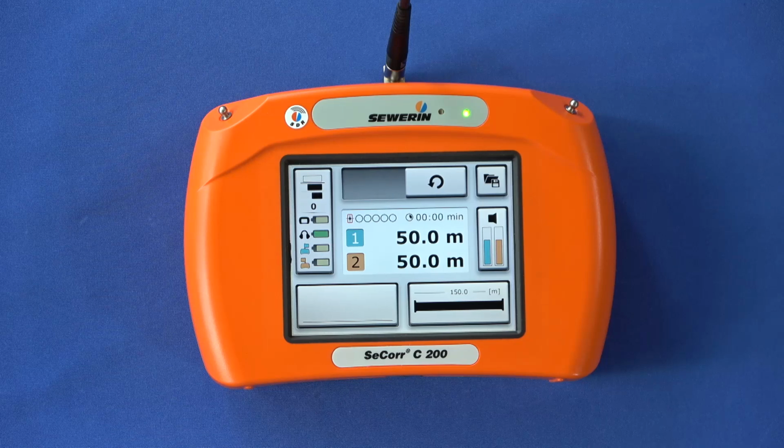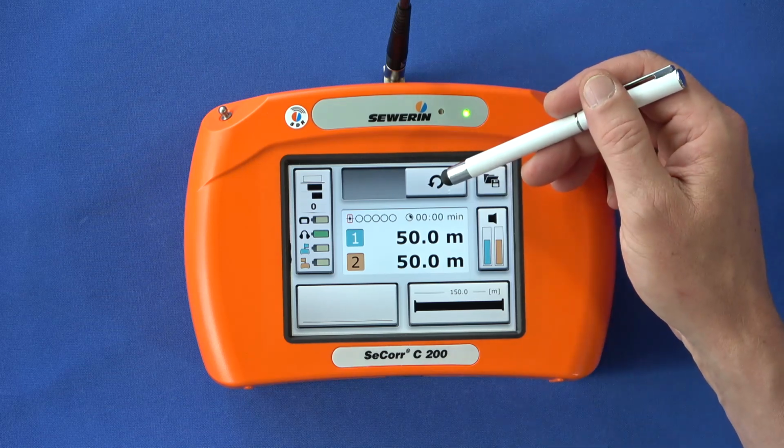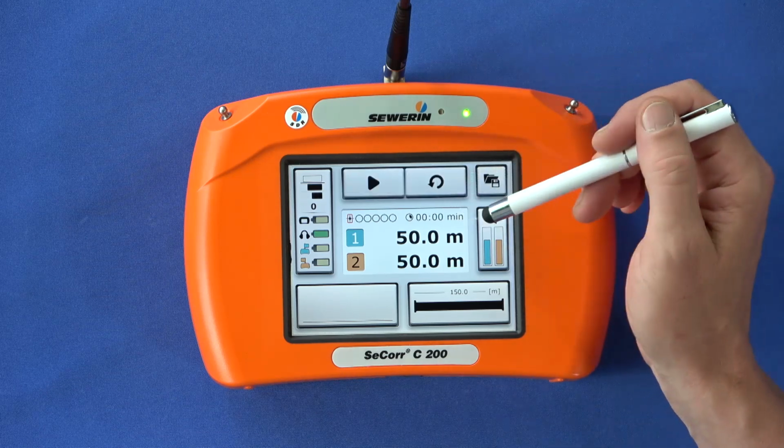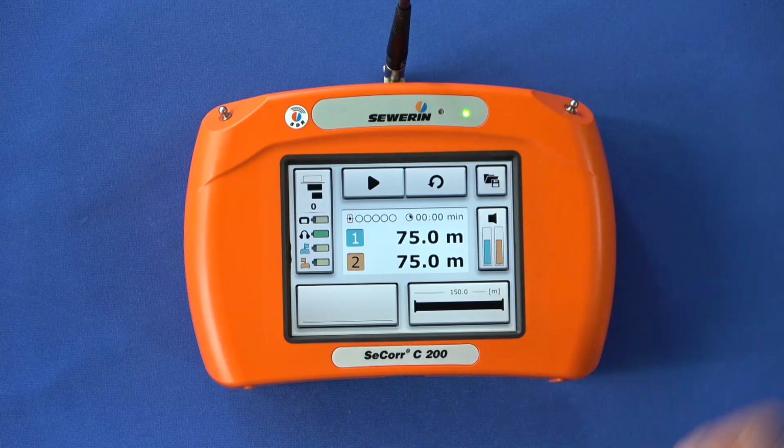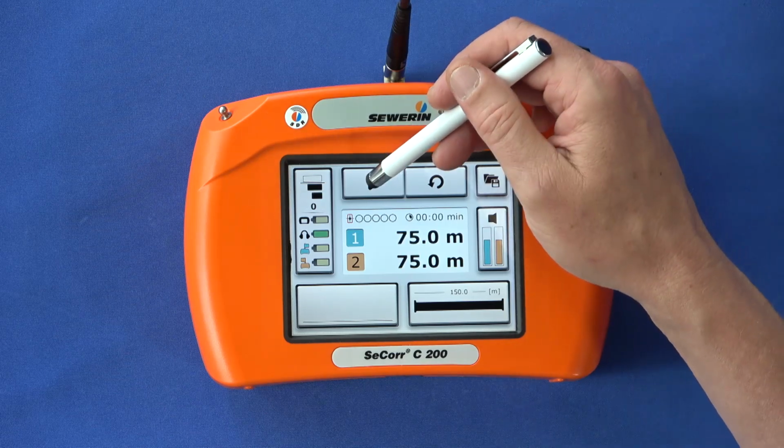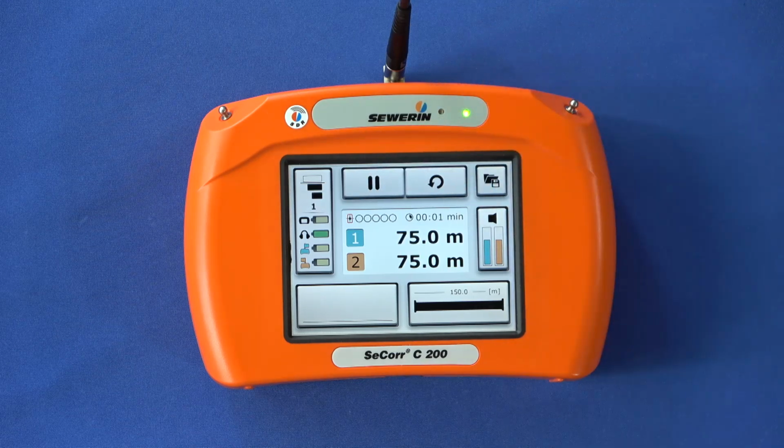You will see the new measurement button above the results field. Tap the button and the measurement is ready to start. The start button appears. Tap this button to start measuring. You should make sure to start the measurement at a moment as quiet as possible, for example if no vehicle drives past the measuring point or if there is no consumption near one or the other connection point.